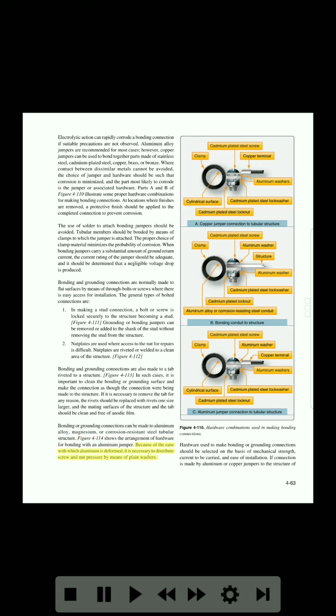Because of the ease with which aluminum is deformed, it is necessary to distribute screw and nut pressure by means of plain washers. Cadmium-plated steel screw. Clamp, copper terminal. Aluminum washers. Cylindrical surface. Cadmium-plated steel lock washer. Cadmium-plated steel lock nut. A. Copper jumper connection to tubular structure. Cadmium-plated steel screw. Clamp, aluminum washer. Structure. Aluminum washer. Cadmium-plated steel lock washer. Cadmium-plated lock nut. Aluminum alloy or corrosion-resisting steel conduit. B. Bonding conduit to structure. Cadmium-plated steel screw. Clamp. Aluminum washer. Copper terminal. Aluminum washers. Cylindrical surface. Cadmium-plated steel lock washer. Cadmium-plated steel lock nut. C. Aluminum jumper connection to tubular structure.